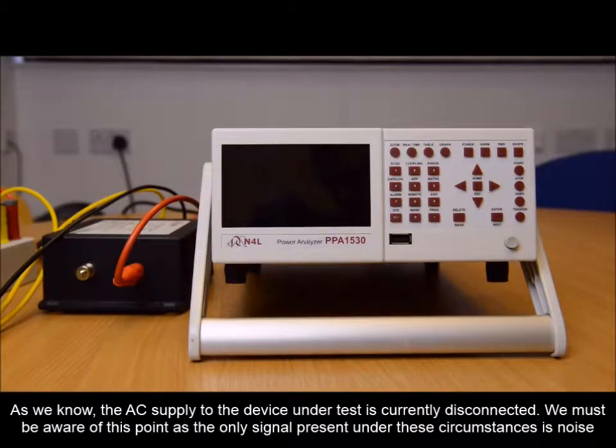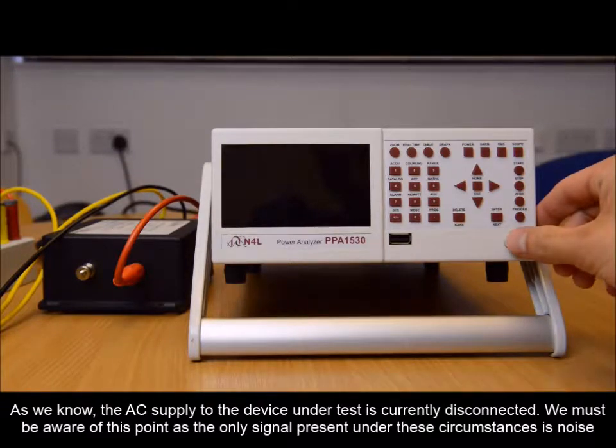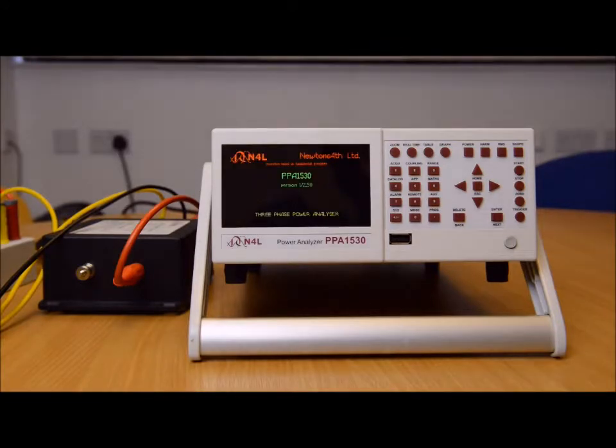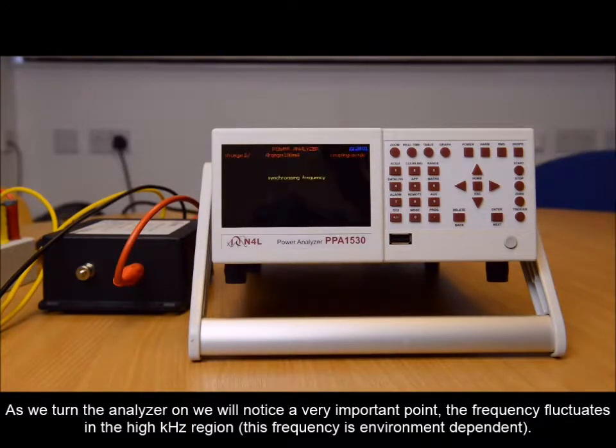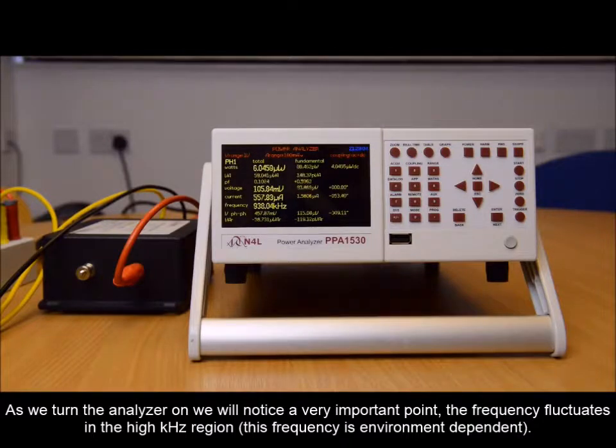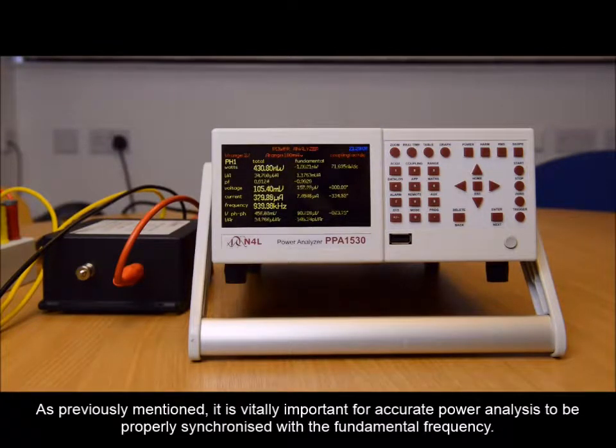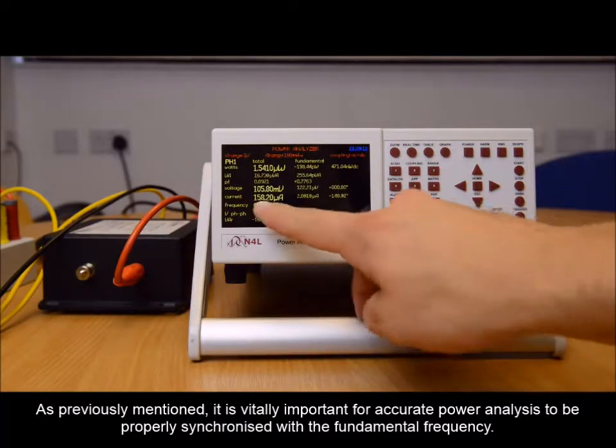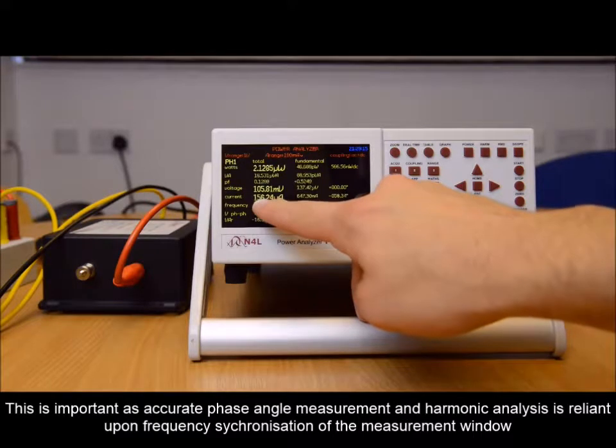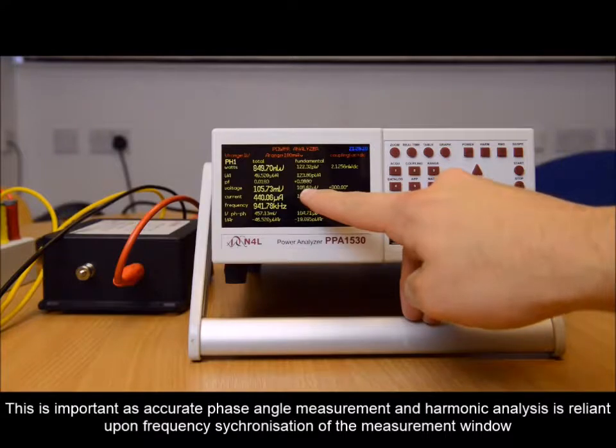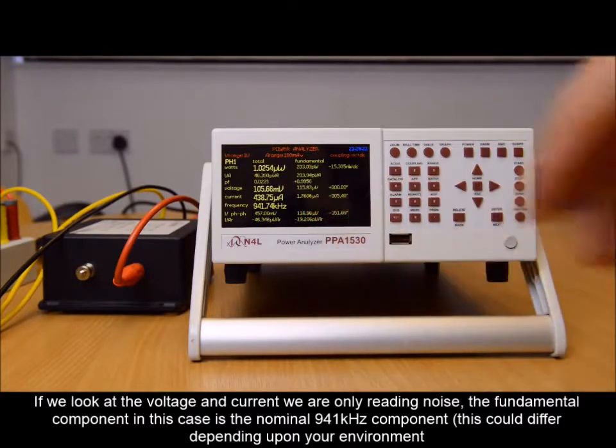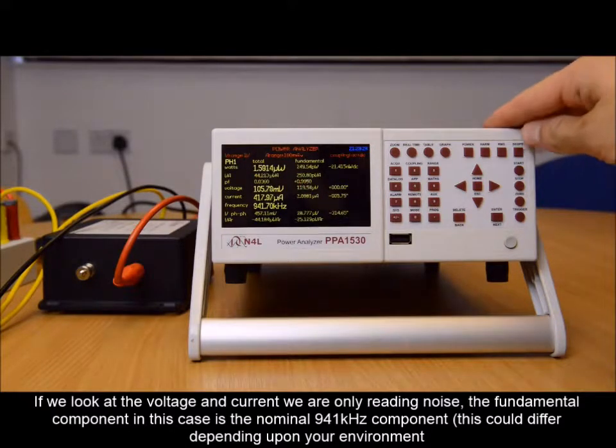As we know, the AC supply to the device under test is currently disconnected. We must be aware of this point as the only signal present under these circumstances is noise. As we turn the analyzer on, we will notice a very important point. The frequency fluctuates in the high kilohertz region. As previously mentioned, it is vitally important for accurate power analysis to be properly synchronized with the fundamental frequency. This is important as accurate phase angle measurement and harmonic analysis is reliant upon frequency synchronization of the measurement window. If we look at the voltage and current, we are only reading noise. The fundamental component in this case is the nominal 941 kHz.